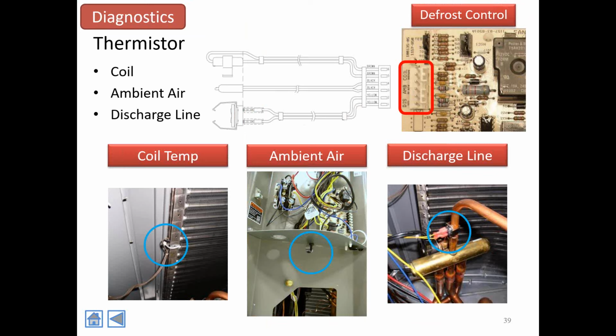All right, so we talked about the sensors that are on here: the coil sensor, the ambient air sensor, and the discharge air sensor. These are 10K ohm sensors. You use a standard 10K ohm resistance chart to test and see if they're reading properly, or even what they're reading. That's something that I want technicians to understand. You can actually put a temperature probe right beside this sensor and see what it's reading.